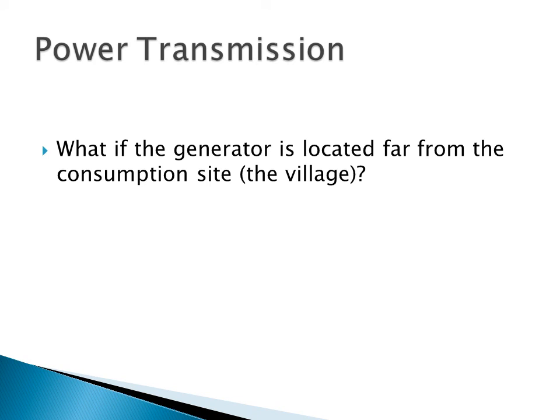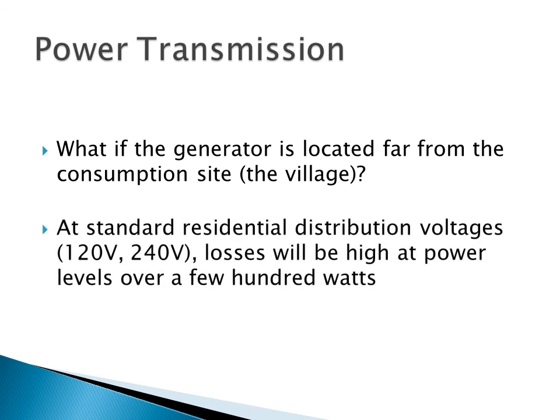For those of you who have taken power courses, you'll be familiar with the problem of transmitting power over larger distances. In this case, where you have a rural village, it's quite likely that the generator could be located far enough away from the village that the losses will be considerable. If you were to use a regular distribution voltage of 120 or 240, the losses will become basically unacceptable at power levels over a few hundred watts.